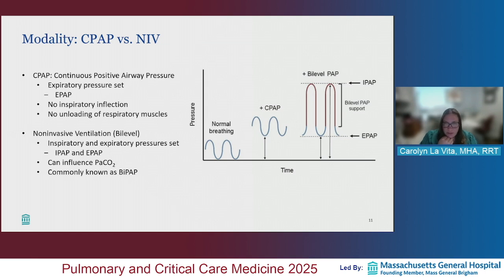Bi-level non-invasive ventilation, BiPAP, they're all interchangeable, which can be incredibly confusing, but it elevates the breathing off baseline again because you are applying CPAP or EPAP. But in addition, it adds an inspiratory pressure or IPAP to really change the patient's CO2, to augment the tidal volume, and to offload some of the respiratory muscles that the patient may exhibit increased work of breathing.